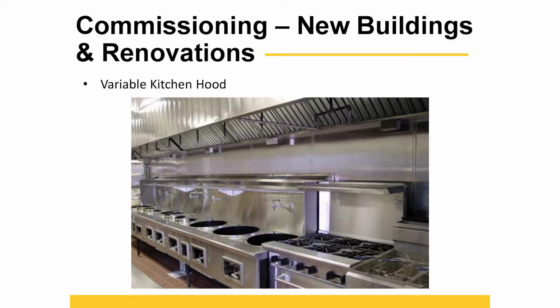The A team had sequences on their drawings. All the controls and information came in and said, yep, we're going to operate this way. So we went out and tested it. It did not work that way. All four hoods were working with both fan coil units. The one fan coil unit ramped before the other, even though they had differing makeup airs to the hoods.